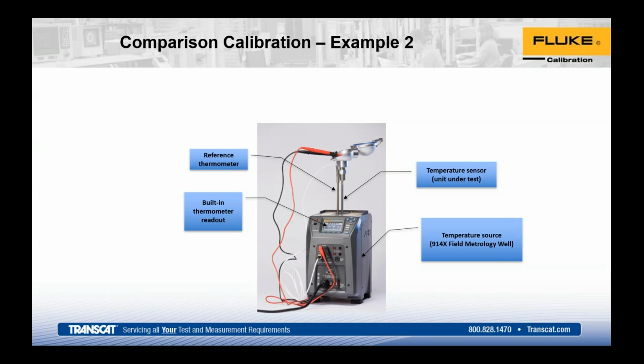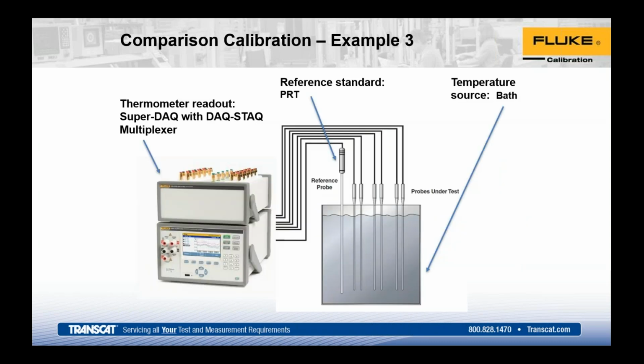And then, building on another comparison calibration example, is moving from, say, a dry well to a bath. Baths typically are used when more stability and uniformity is needed. This allows for more throughput, and the reason for that is typically the fluid volume allows for this. So when you're investigating a bath versus a dry well, we'll touch on those as we continue on.